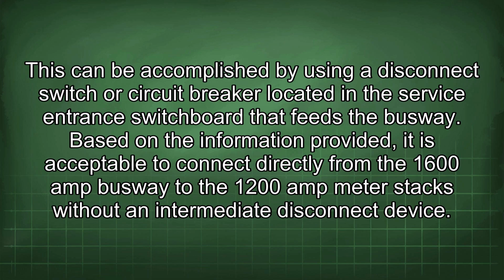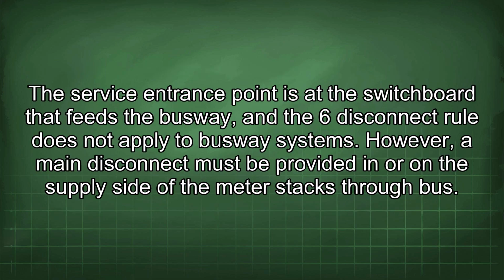feeds the busway. Based on the information provided, it is acceptable to connect directly from the 1600 amp busway to the 1200 amp meter stacks without an intermediate disconnect device. The service entrance point is at the switchboard that feeds the busway, and the 6 disconnect rule does not apply to busway systems. However, a main disconnect must be provided in or on the supply side of the meter stacks through bus.